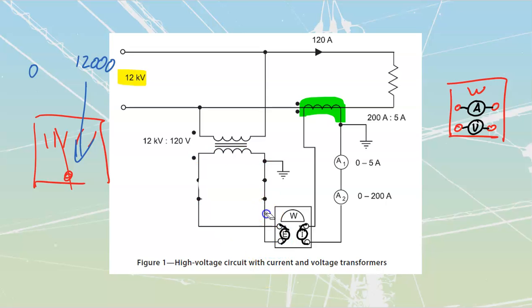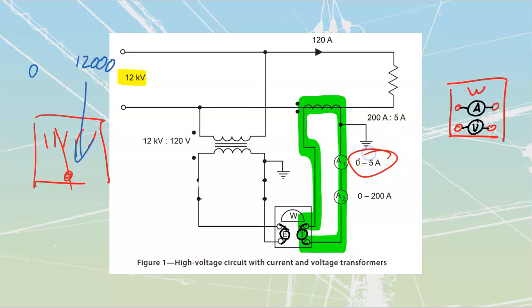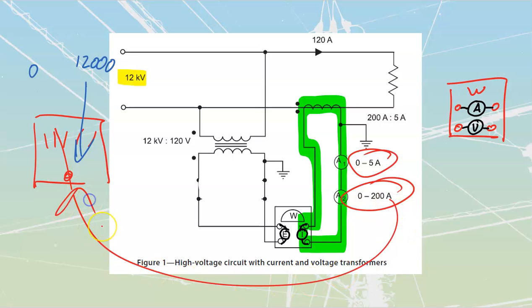And a watt meter needs to read both voltage and current. My ammeter has a complete current path. I've grounded it down once again, and we will cover that later on, but I've got complete current that is going to flow through each one of these ammeters. It's a series circuit because we're looking at amperage. Every single one of these has to be connected in series. What I'm going to have out of it as well is, once again, dual meters. One that's going to tell me what my actual current is coming from the CT. The other one is going to have a different piece of paper, scaling it across to 200 amps, because it would otherwise take a little bit of math to see where our system is instantaneously at.